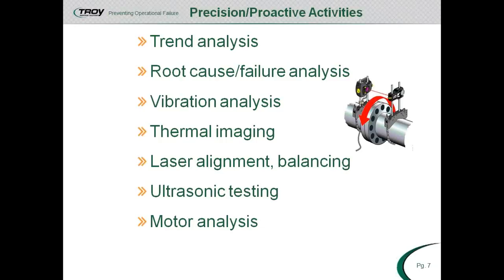That makes it very valuable information because we know where we took the image, we know where we were because of the voice annotation put on it, and then it can be rapidly put into a report format. The thermal imaging may give us signs of a rub or friction. You can look at 2 driven bearings. One, it'll show a differential between the 2. The suspect bearing could possibly be overheating. Alignment problems can be seen with thermal imaging, but it's really very helpful with electrical anomalies such as a looseness or an overloaded lug, corrosion in connectors. They'll show up very well with thermal imaging.